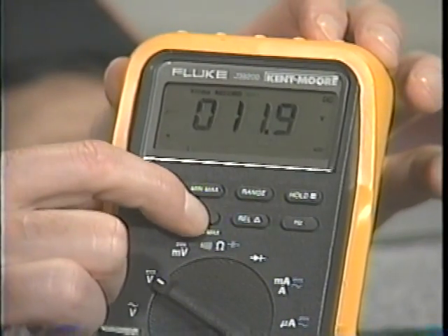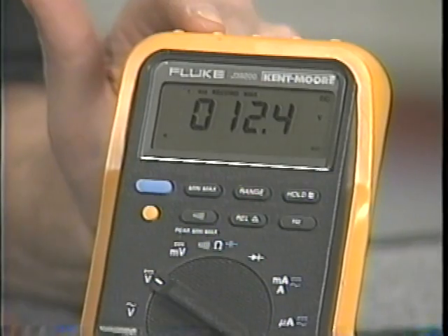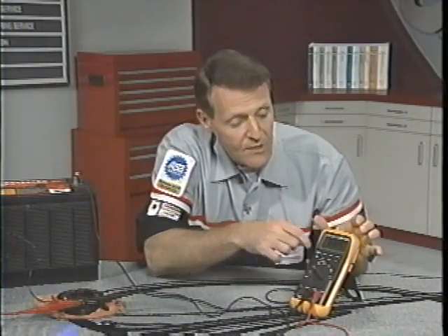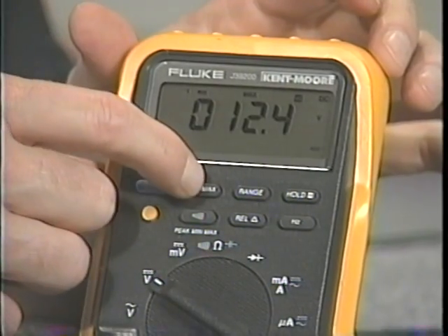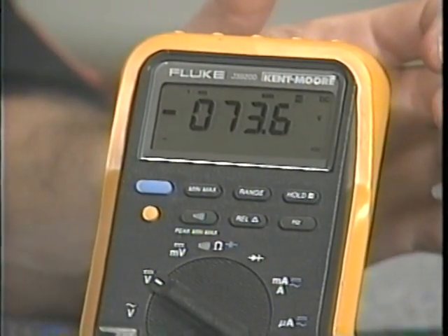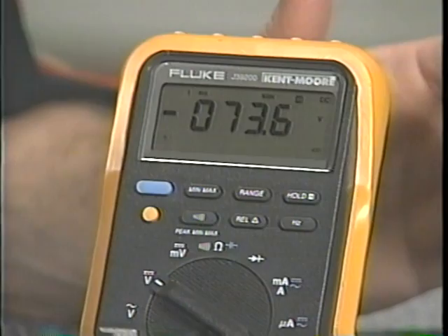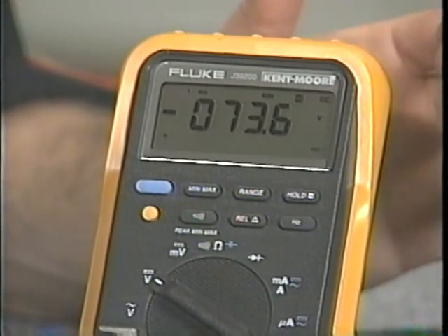Peak MinMax can catch values that last for just 1 millisecond. To enter peak MinMax, you have to be in MinMax, and we're already there. So I'll press the beeper button, and the meter's recording again. Now I'll break the coil circuit again. Press hold to stop the recording, and press MinMax to view the results. Minus 73.6 volts. There's our spike.